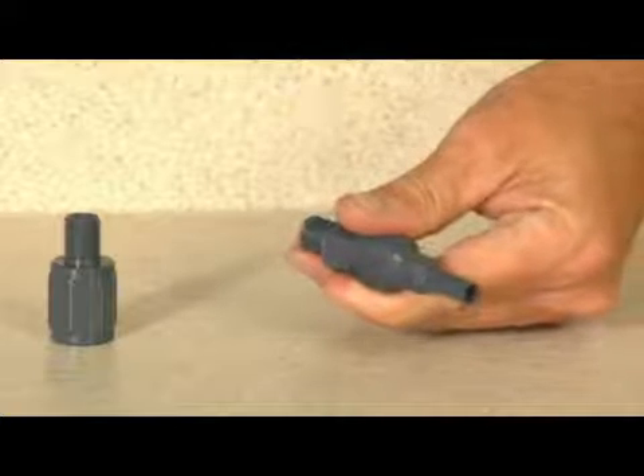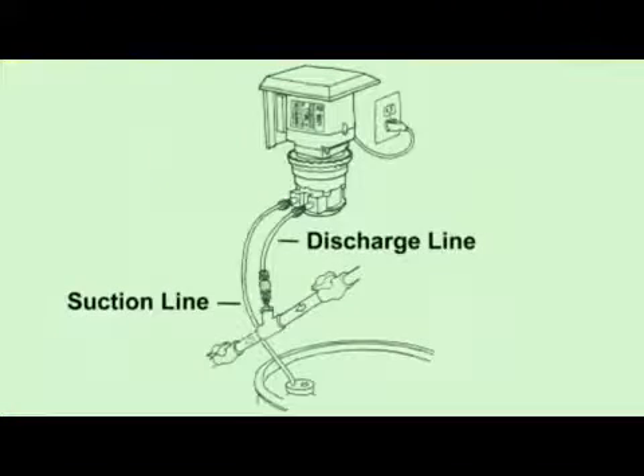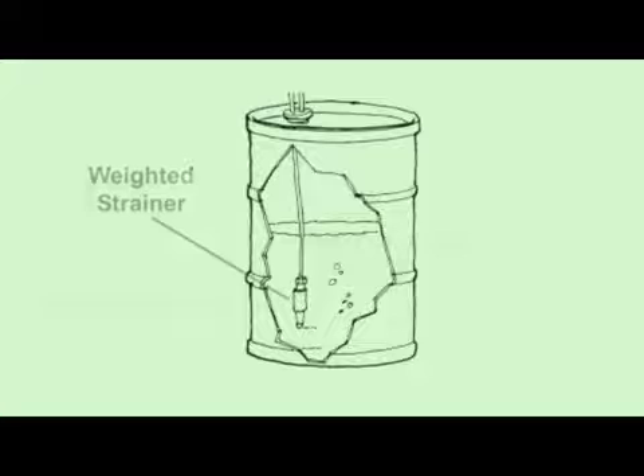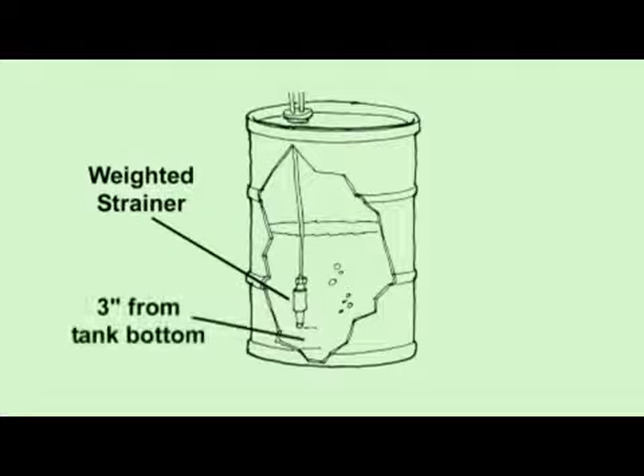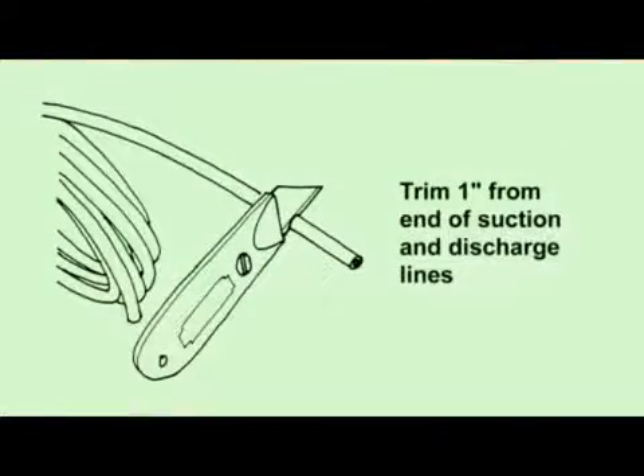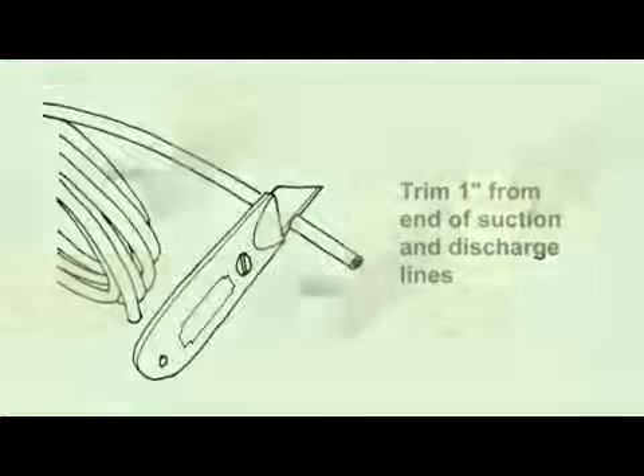Do not drill through the opposite pipe wall. Replace both the suction and discharge tubing and clean the sediment from the tank bottom. Install the Stenner weighted strainer if not using one, and be sure it's 3 inches from the tank bottom. Replace the duckbill. And at every tube change, trim approximately 1 inch off the end of both the suction and discharge lines before installing the new ferrules.